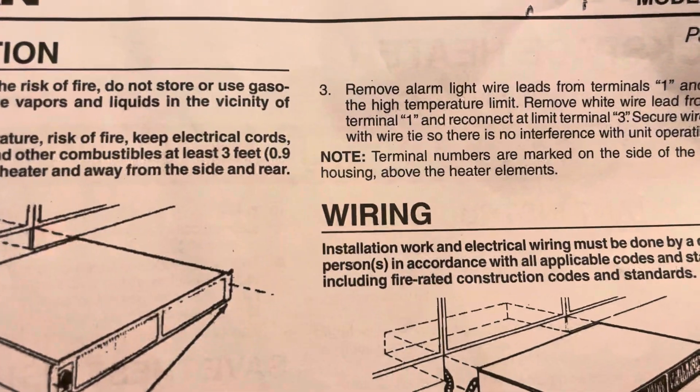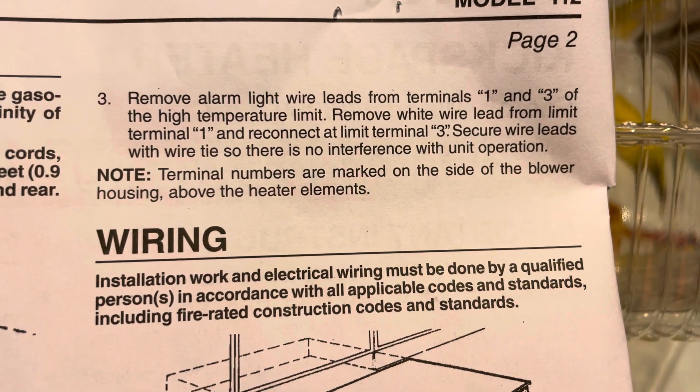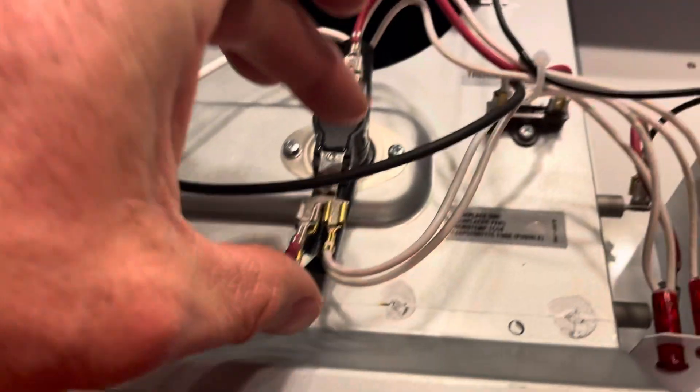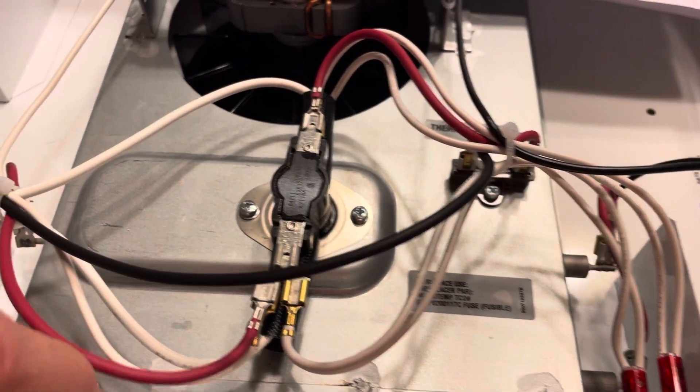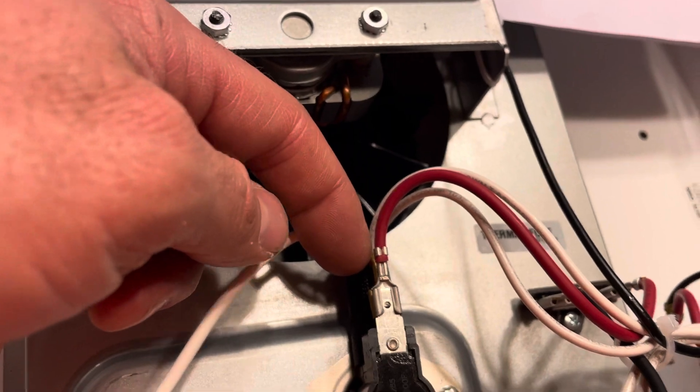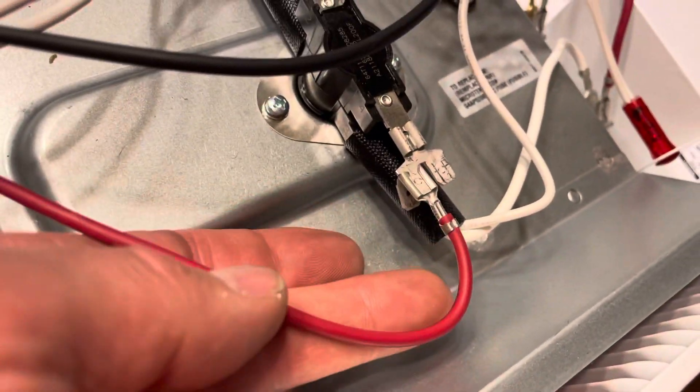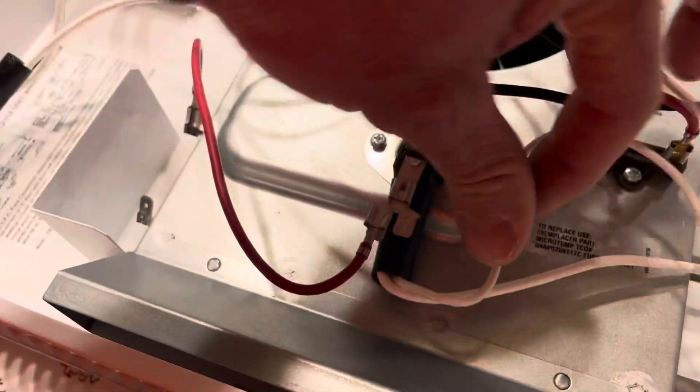So this one here is the one they're talking about: remove white wire lead from limit terminal one and reconnect it at limit terminal three. So we disconnect this white one here from terminal one, which this is terminal one, you unplug this wire and you plug it in back over here underneath where the other light was plugged in. We can see that we've done that here.